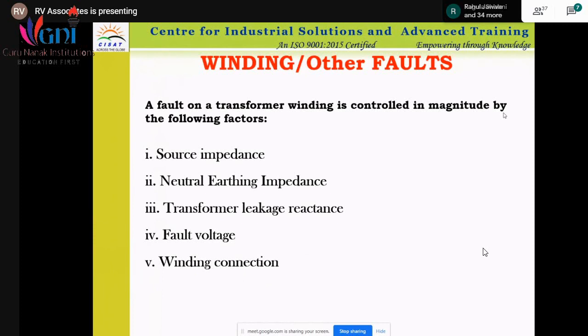Then these faults in the winding, what we call the internal faults of the winding, can be controlled by the source impedance, neutral earthing impedance, transformer leakage reactance, fault voltage, or winding connections. Winding connection, when we talk about the transformer, can be a star-delta transformer. So based on the requirement, the connections can be star or delta.